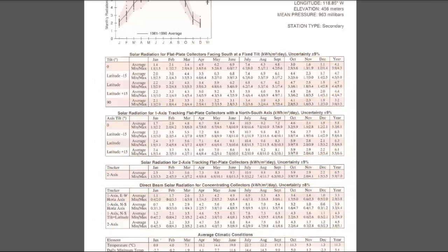The numbers in the columns are in units of kilowatt hours per meter squared per day and are equivalent to peak sun hours. This is the number you use in addition to the power rating of your array to estimate energy production performance. The differentiation between the 4 datasets obviously refer to the means of mounting PV panels. Regardless, every single one of these datasets assume the PV panels are pointed due south, and alternate orientations need to be accounted for via T&O charts or other means. This topic is covered extensively in the PV system solar site analysis tilt and orientation lecture.